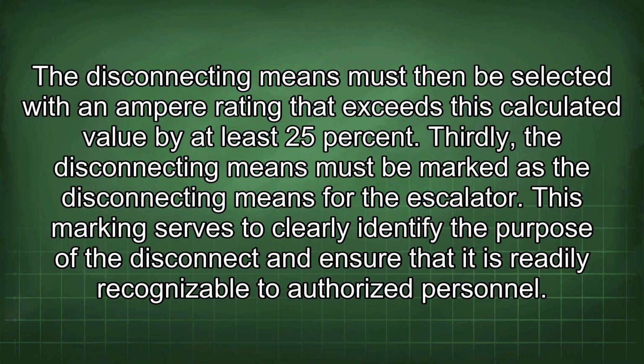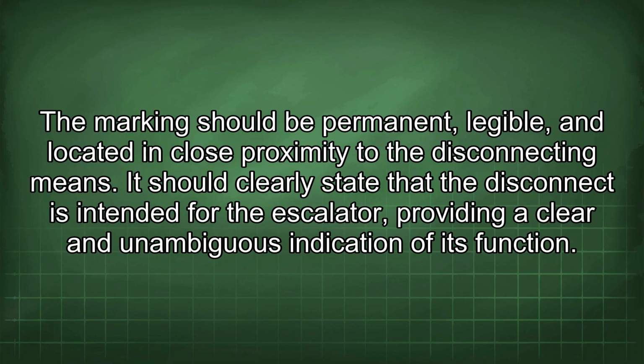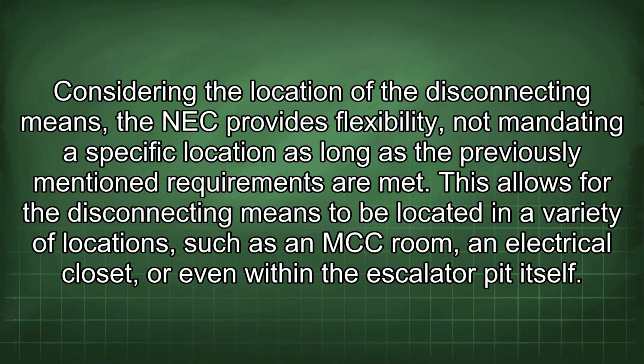This marking serves to clearly identify the purpose of the disconnect and ensure that it is readily recognizable to authorized personnel. The marking should be permanent, legible, and located in close proximity to the disconnecting means. It should clearly state that the disconnect is intended for the escalator, providing a clear and unambiguous indication of its function. Considering the location of the disconnecting means, the NEC provides flexibility, not mandating a specific location as long as the previously mentioned requirements are met.